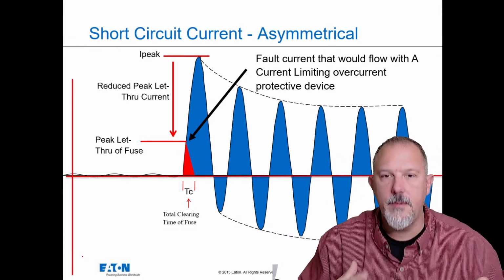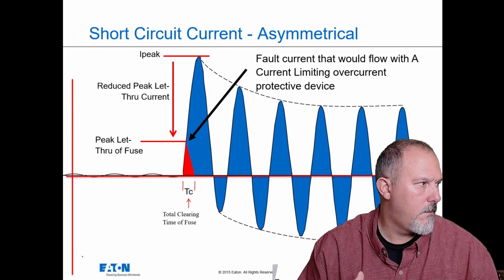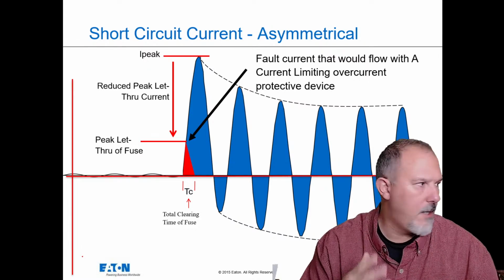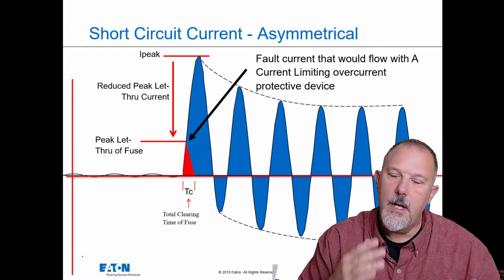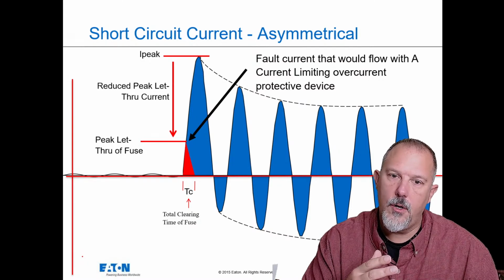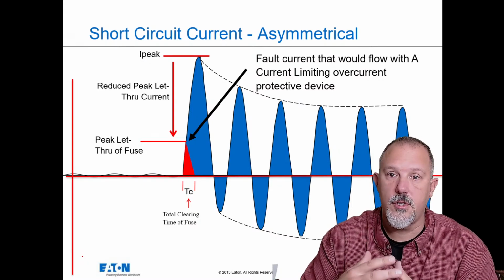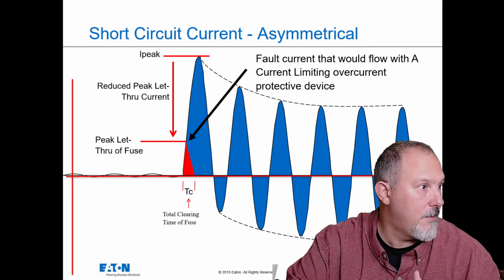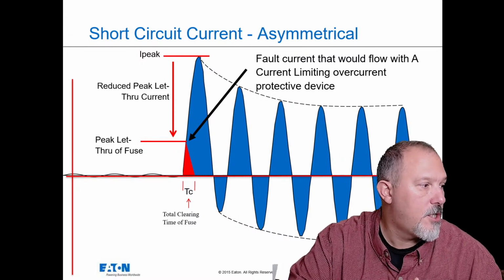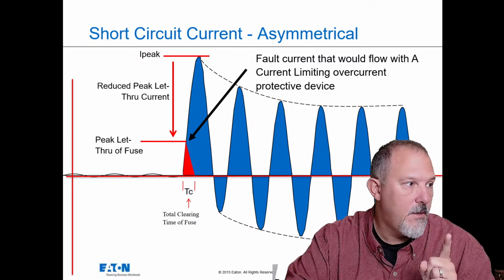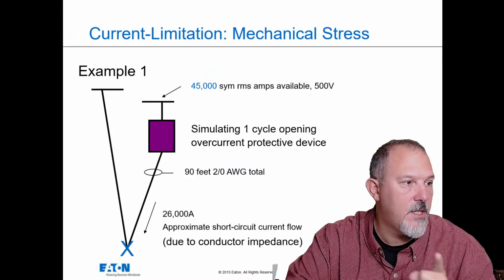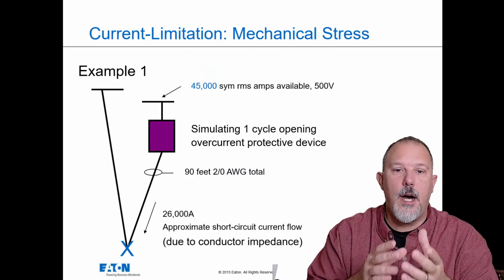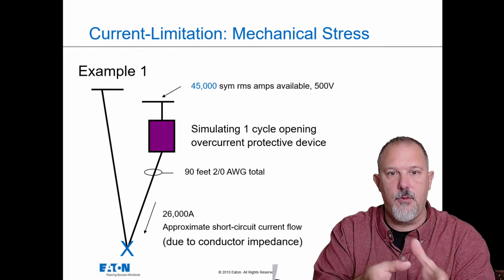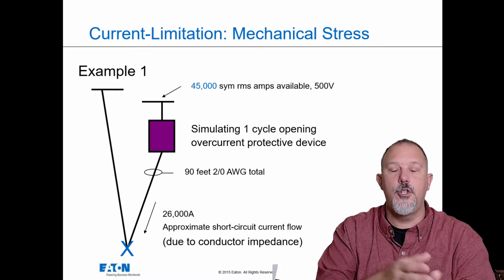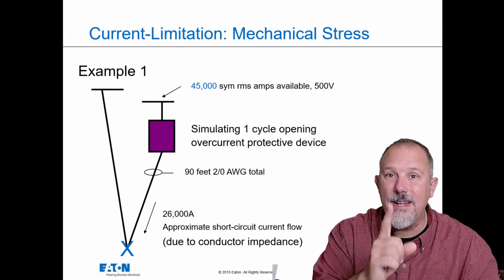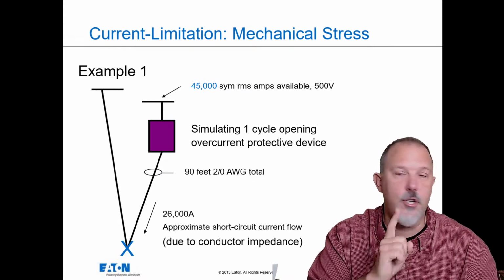So in current limitation, I am reducing the force on the power distribution system. So what does that mean from a short circuit current rating perspective? Let's run this example. I have 26,000 amps passing through a conductor. I have one cycle of fault current flowing.